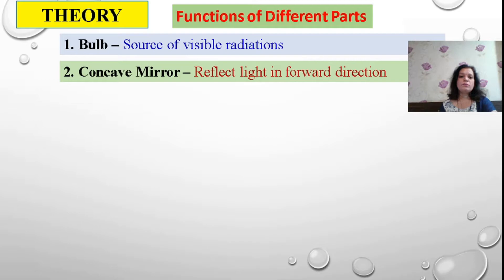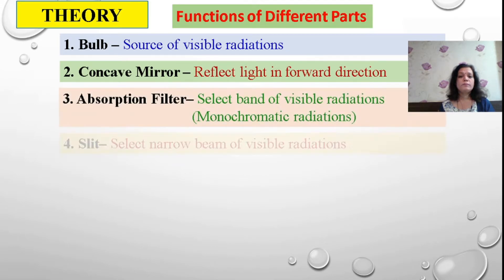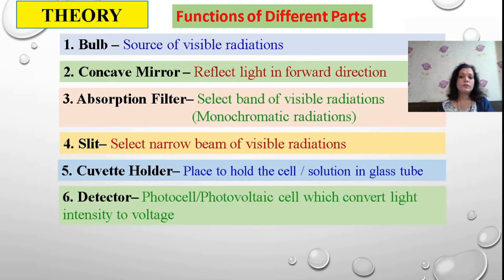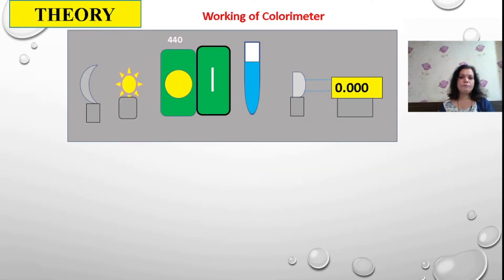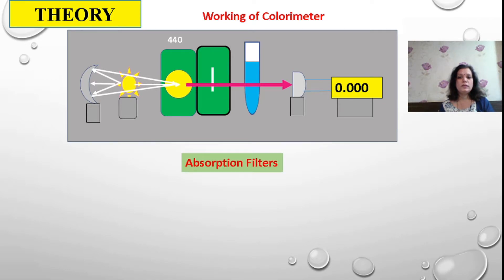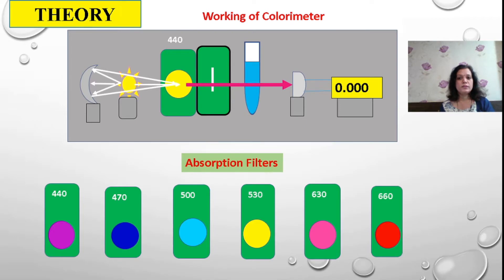This bulb acts as a source of light. A concave mirror reflects light in the forward direction. Absorption filters are made up of two glass sheets embedded with inorganic colored pigment — that is the process to form the absorption filter. Then slits, then a cuvette holder to hold the colored solution, a detector where a photo cell or photovoltaic cell is used, an amplifier, and a display. When you give the source of light to the filter, it passes through the colored solution and the digital display shows you the reading. These are the inbuilt absorption filters usually placed inside the colorimeter.